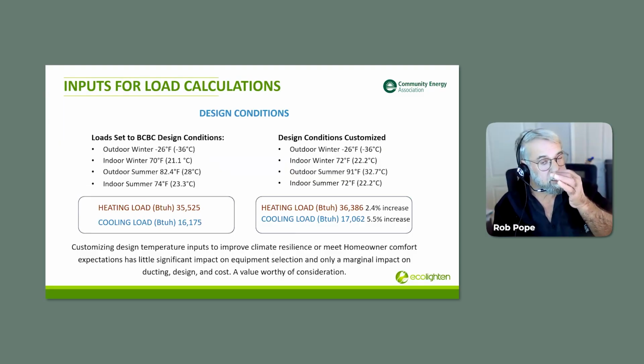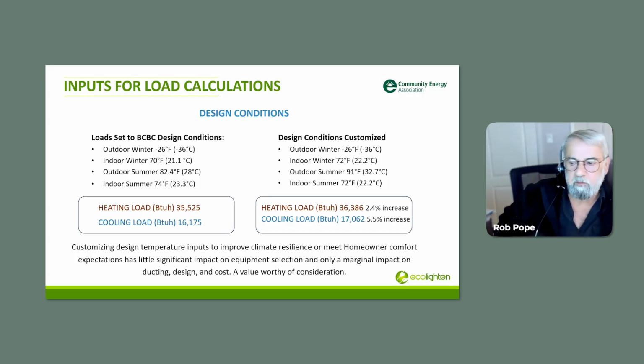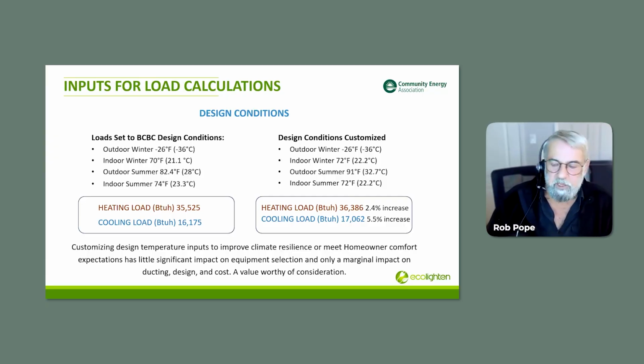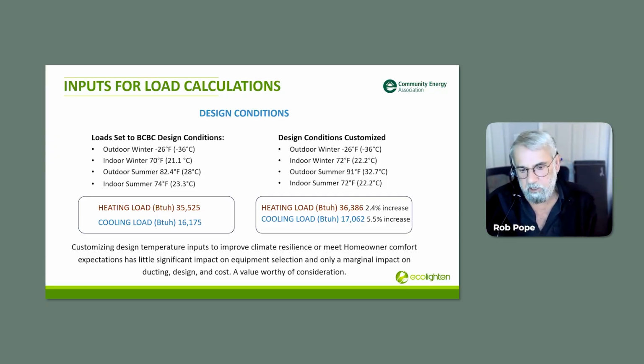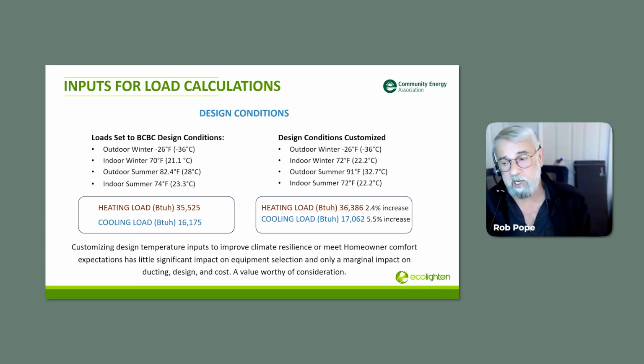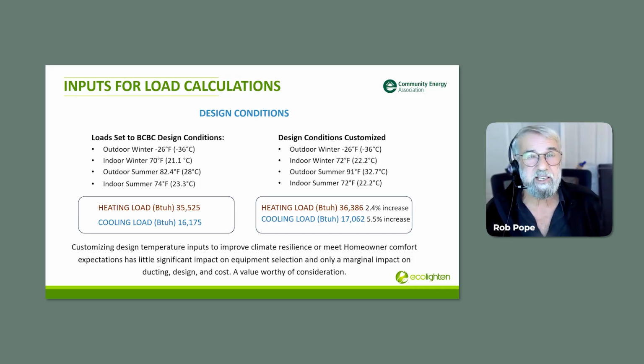Well, that's another reason this is what coordination is all about. If it were me, I would say, okay, here's the situation. Technically, we're just a few hundred BTUs over the 3-ton unit. I think we can get away with a 3-ton unit. What that might mean is that we put in a little more auxiliary, or maybe we didn't have it. Maybe you've got a fireplace. Maybe you just expect there's going to be a few days where you're going to put a sweater and some slippers on. What do you think? And then the homeowner will answer that question, and you can go from there, right?